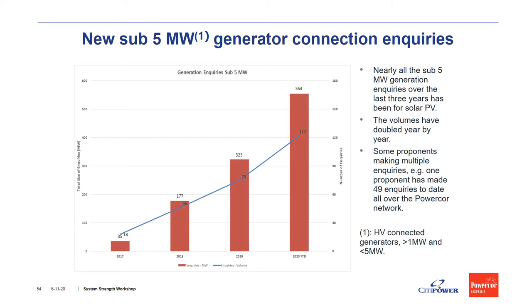Now, I would like to talk about another challenge that we have been dealing with in our network. Since 2017, we have seen an increasing level of interest to connect small-scale or HV connected generators larger than 1 megawatt and smaller than 5 megawatt in our network. Nearly all of those sub 5 megawatt generation inquiries have been for solar PV, so inverter-based generators. And as you can see in the graph, the volume has almost doubled year by year.